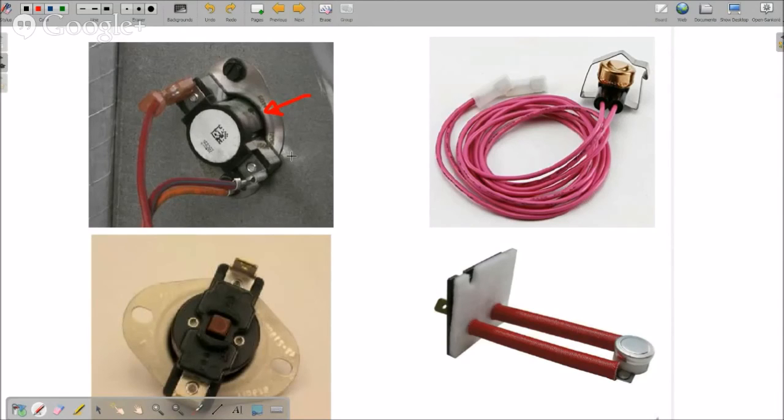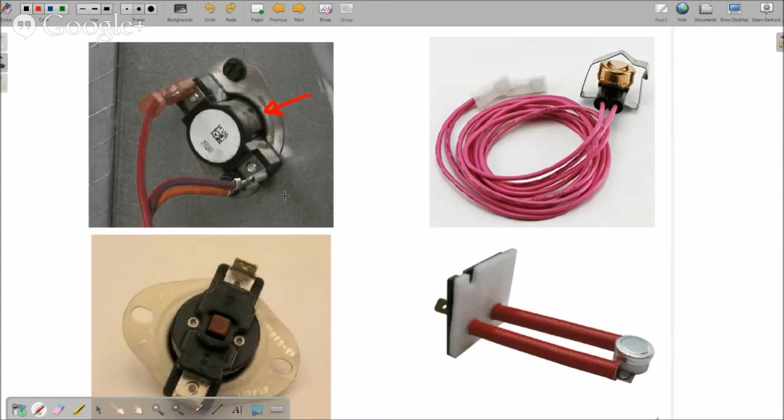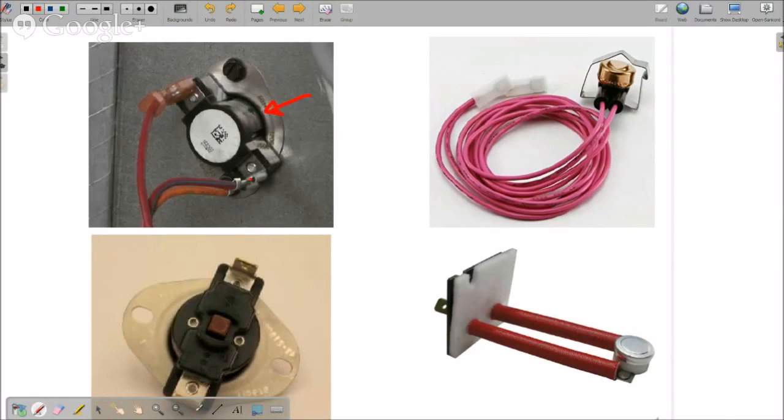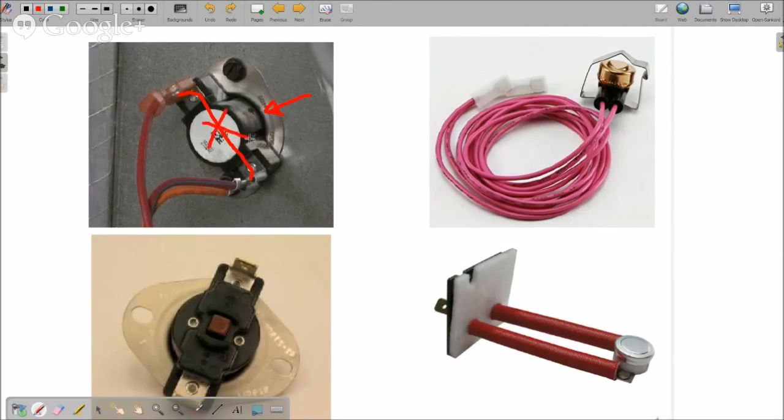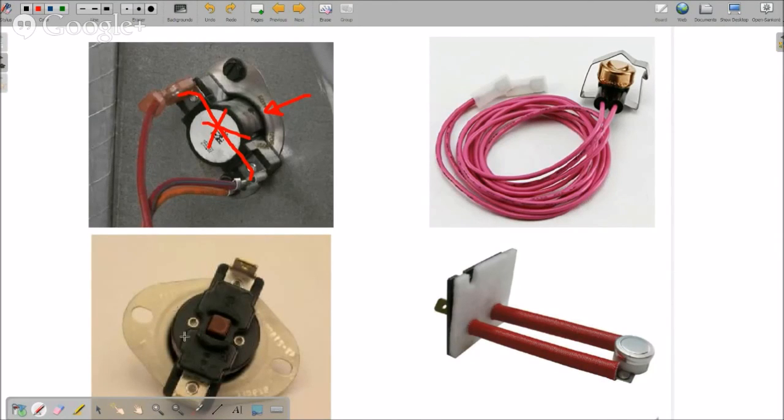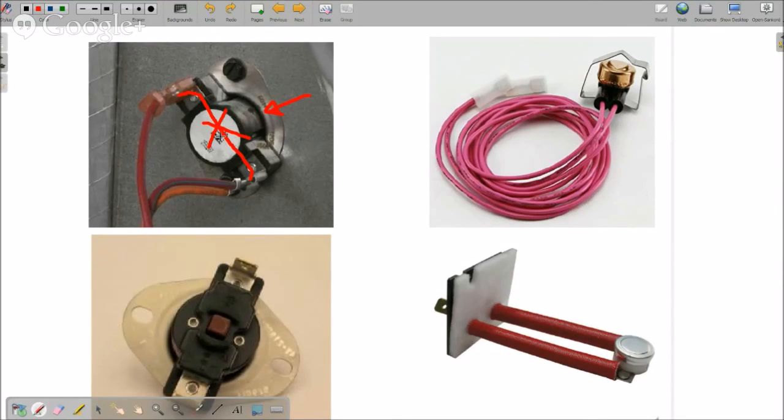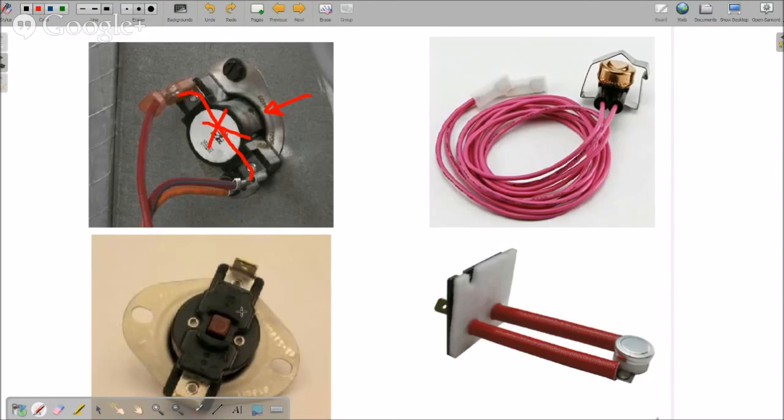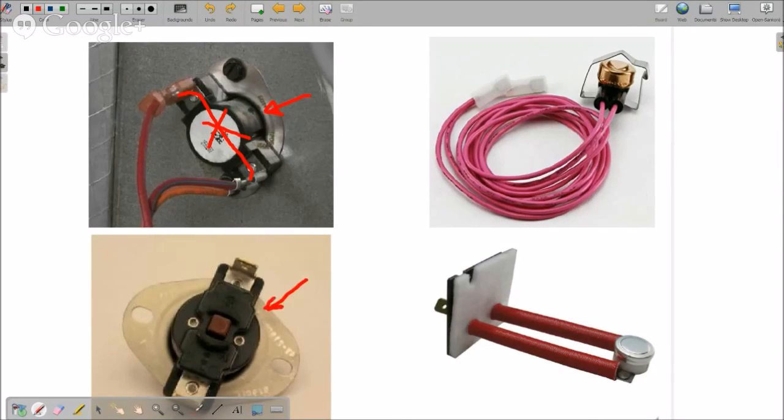Usually these switches are used for safeties. If something gets too hot, it's going to open up and break that circuit. So in this switch, if it gets too warm, this is going to break open the circuit and disable whatever it is controlling. Here's another one, same thing. This is manually reset. Some of them will reset when the temperature comes down, but this one pops and you have to manually reset it. That's a safety switch for sure.